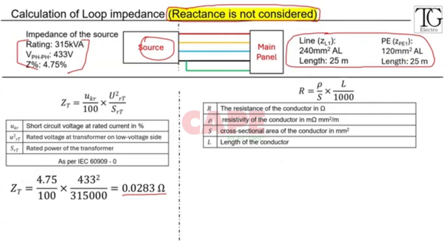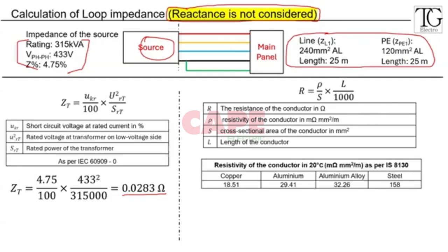Then the resistivity of conductors at 20 degrees is given in the IS 8130 standard. In IS 8130, copper at 20 degrees is 18.51, aluminum is 29.41, aluminum alloy is 32, and steel is 158. If you are using GI as the PE conductor, then you can use this resistivity value.